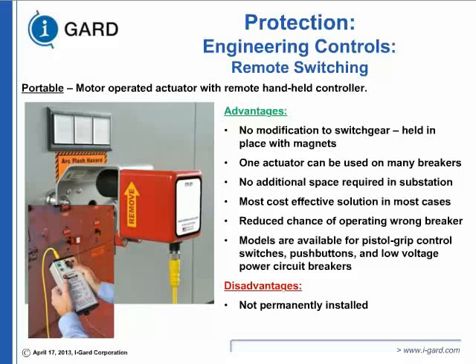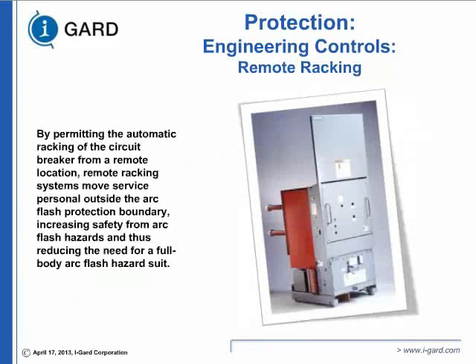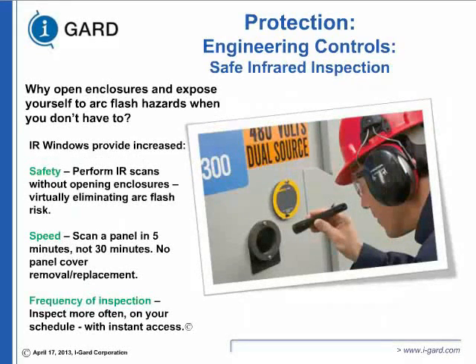Okay? You can remote rack it. Most of the accidents happen whenever electricity changes state. A remote racking device can be installed to do it from a remote location. Okay? You can install infrared windows. They can prevent an incipient fault, that you can see, as opposed to opening the doors. So you can see there are a lot of safety precautions available that you can consider.